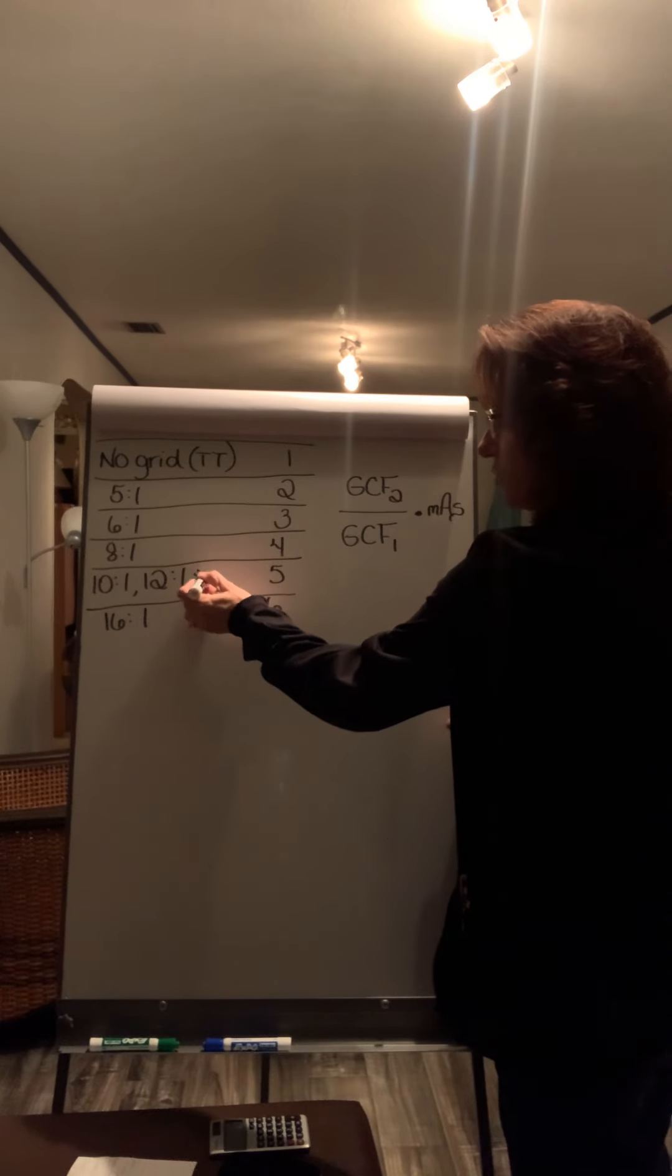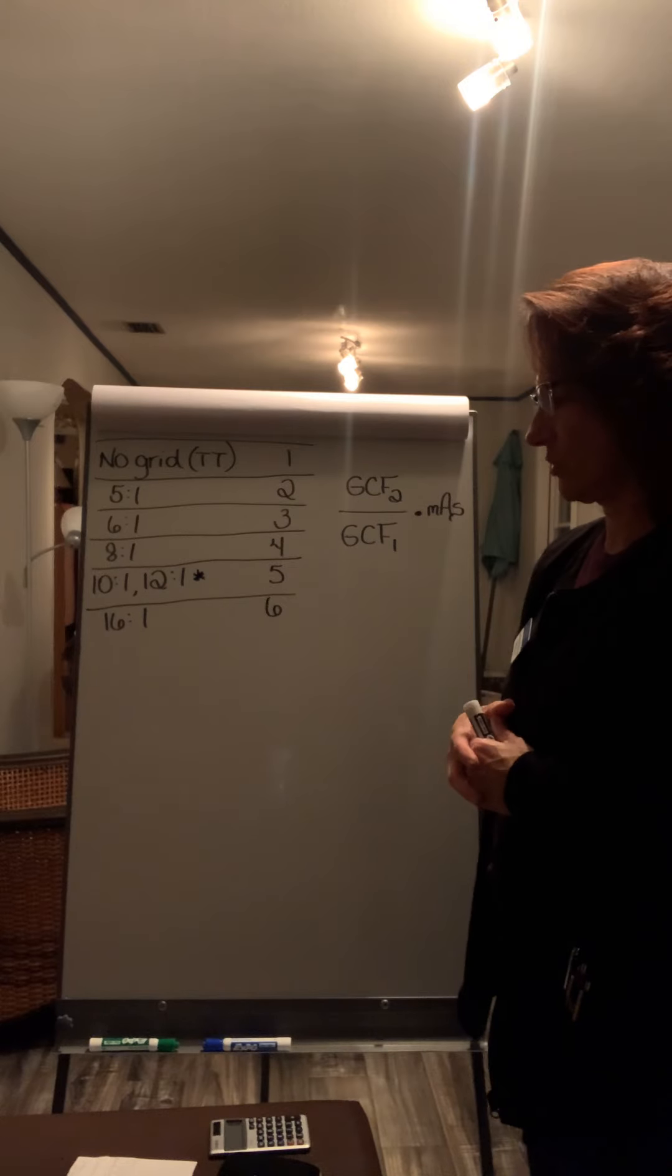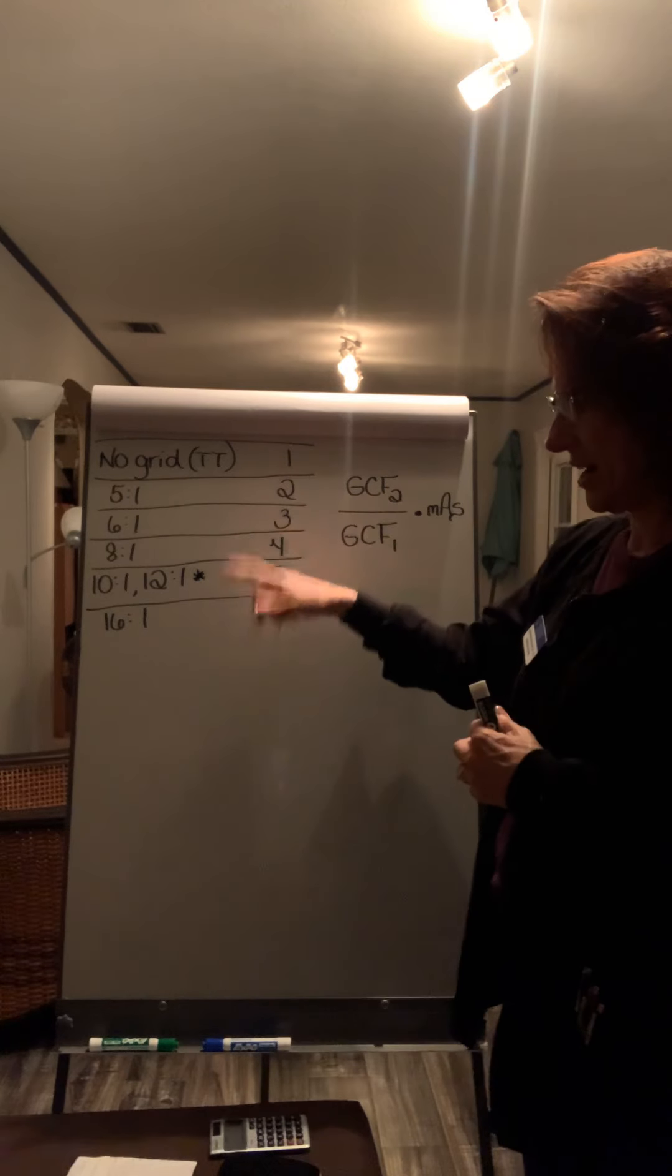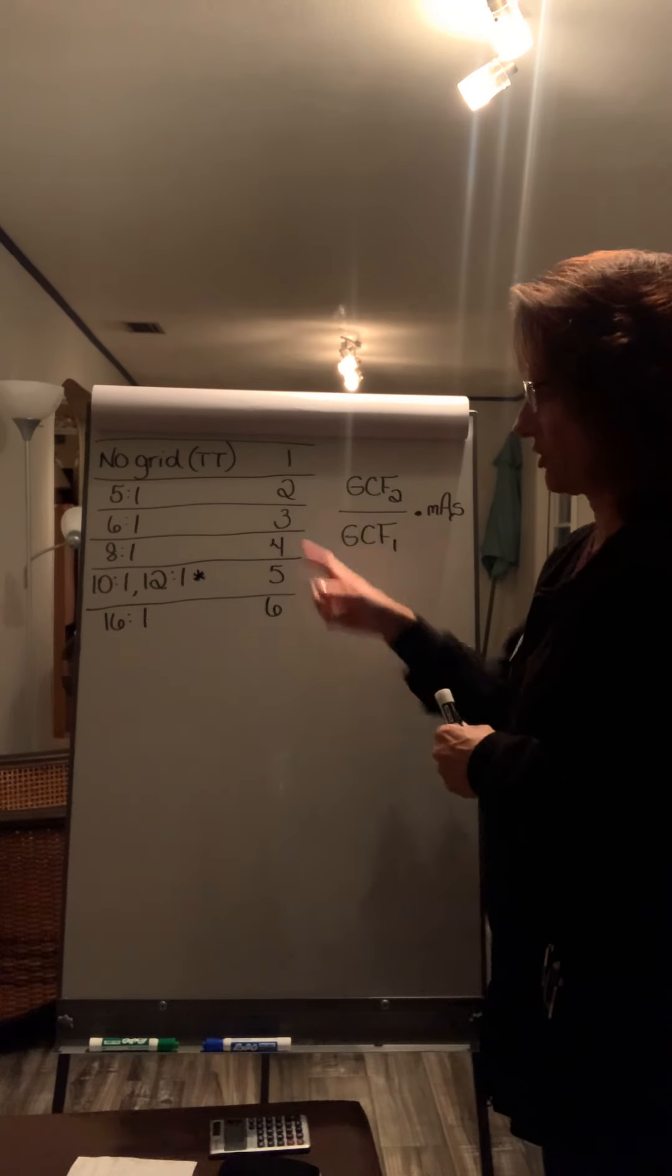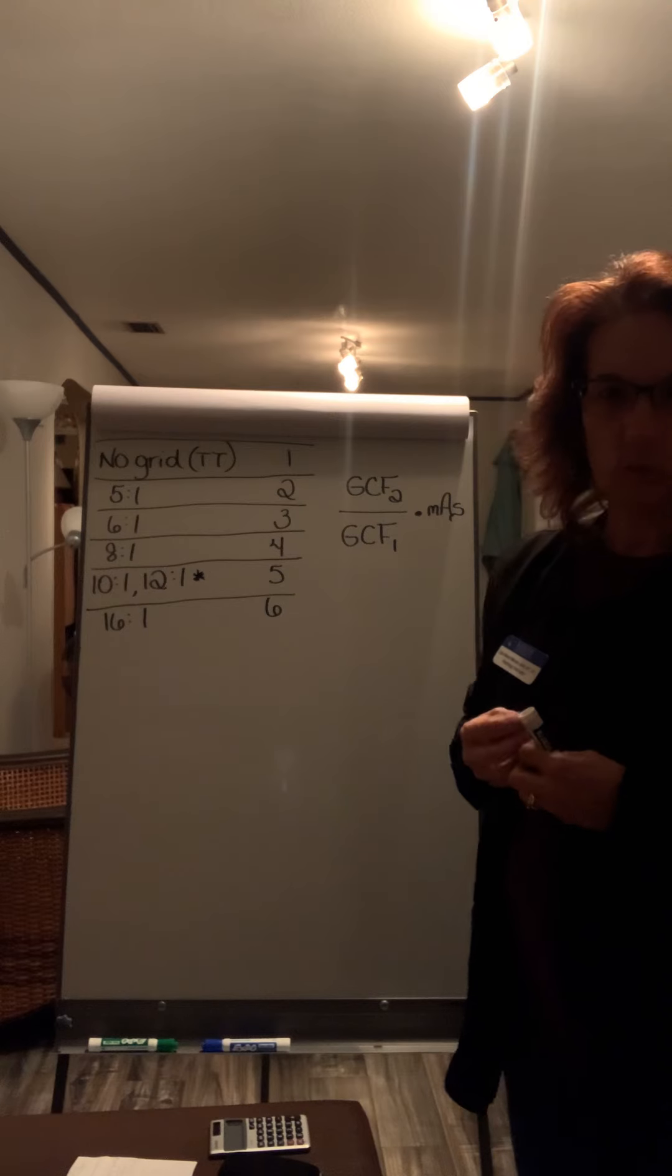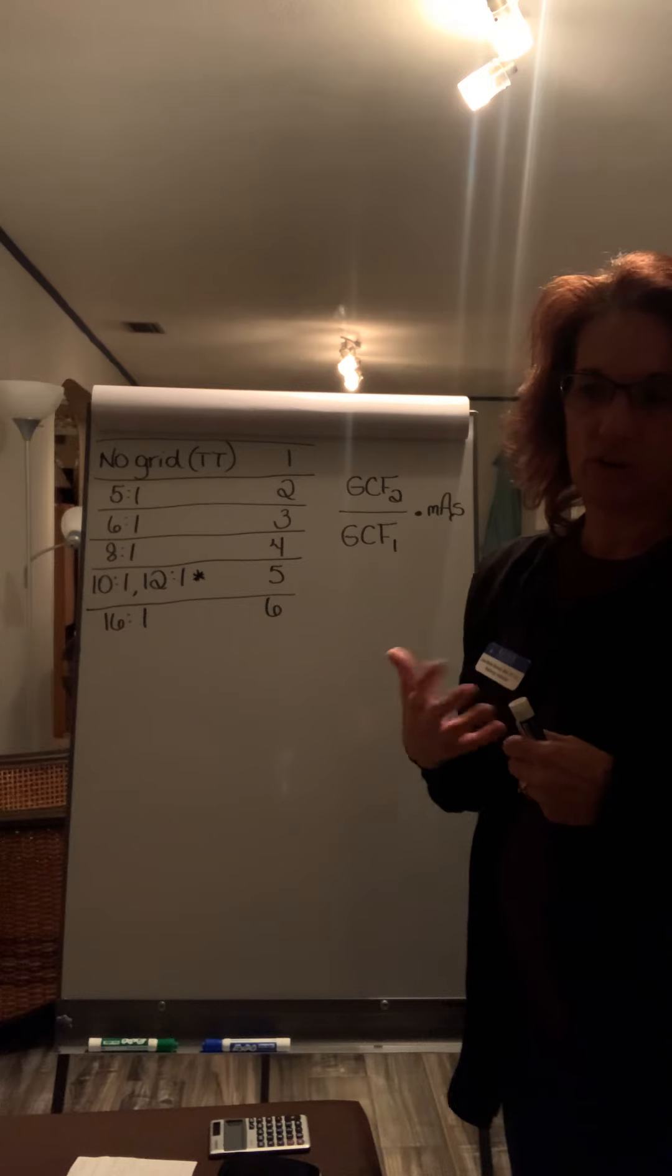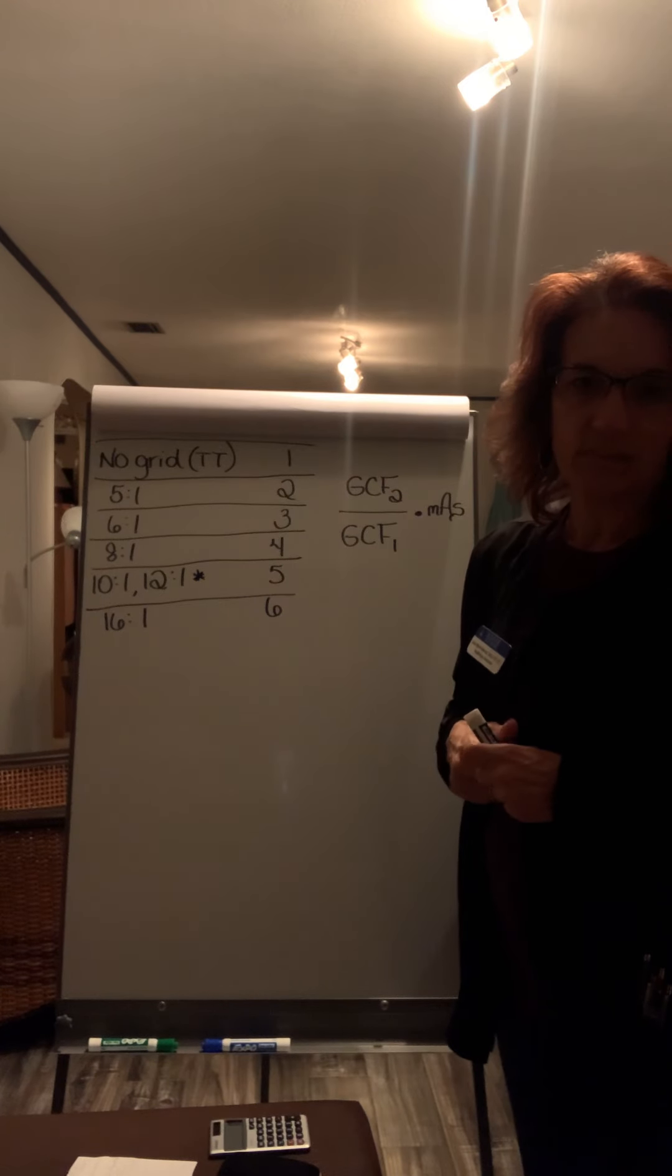Now the significance about the 10 and 12 to 1 is that most wall buckies and table buckies are either 10 or 12 to 1 grid ratios. The lower the grid ratio means there's less lead content in there. So they clean up scatter, but not as well as a higher grid ratio. When you're using tabletop, you don't need a grid. That's why it's the lowest grid conversion factor. But the higher up you go in grid ratio, not only is there more lead in the grid, but you also have to be more precise with your positioning, meaning that any angulation of the grid or misalignment in relation to the part or the photons can cause grid cutoff. So the higher the grid ratio, more lead content, and the more precise you have to be in your positioning.